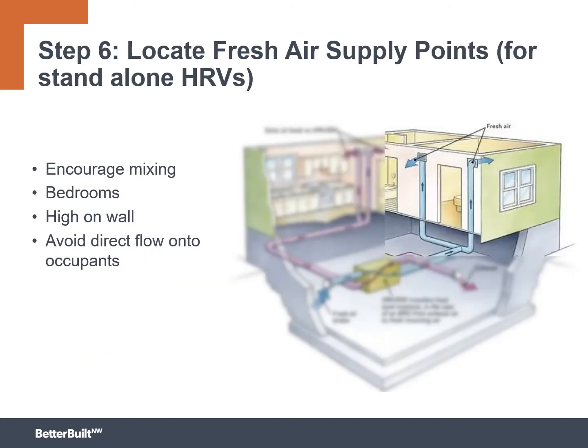Now we have to think about where we are going to supply the new air into the home. In particular, we're talking about standalone heat recovery ventilators. Integrated ones, of course, are supplying the air through the heating and cooling ducts in the home. So in a standalone HRV, we want to encourage as much mixing in the house as we possibly can. We'd like to get it into bedrooms, maybe even high up on the wall. And we want to avoid direct flow onto occupants. So, you know, grandma is sitting in a rocking chair, even if that incoming air temperature is in the 60s and not the 30s, it still may not feel comfortable to her.